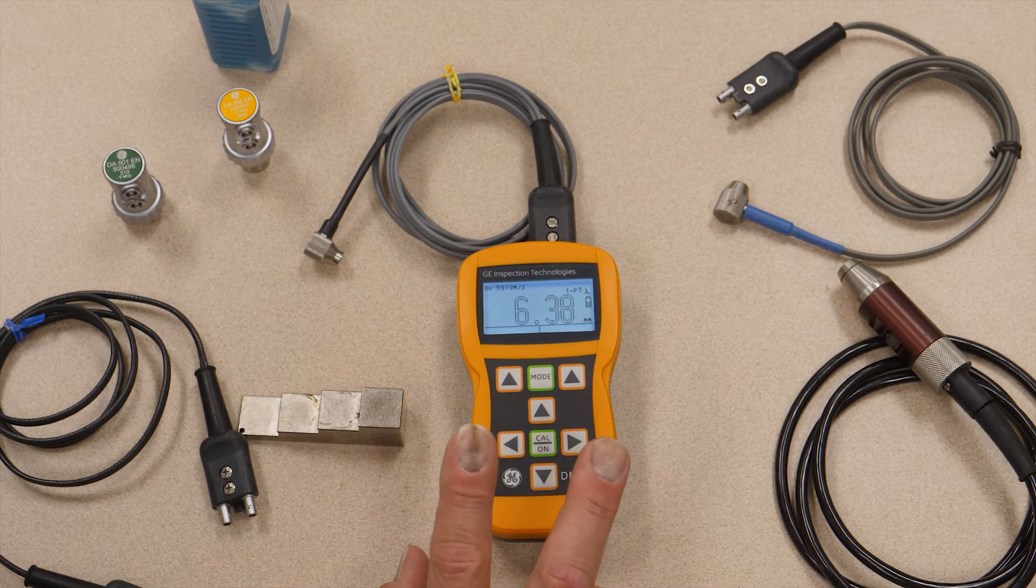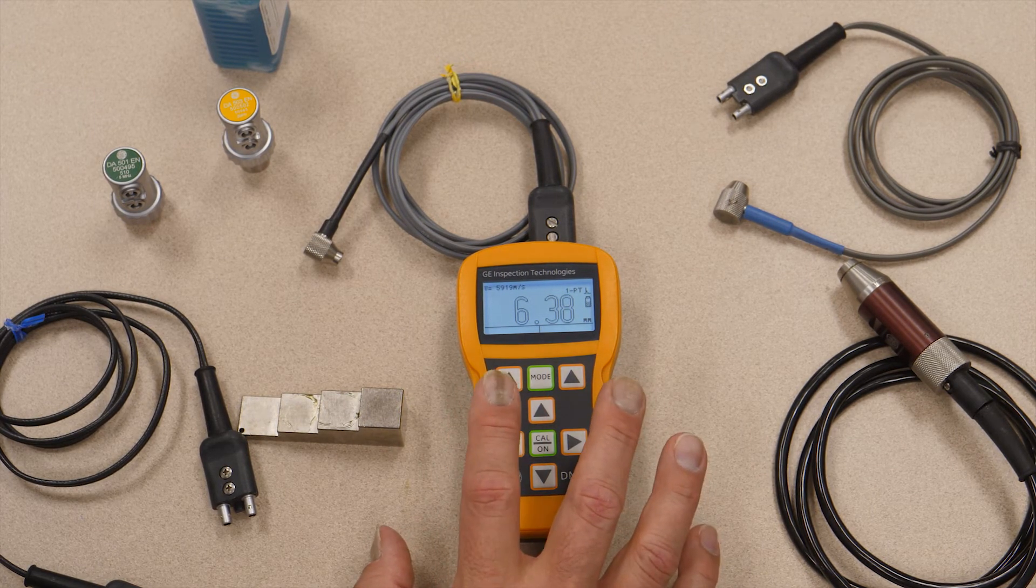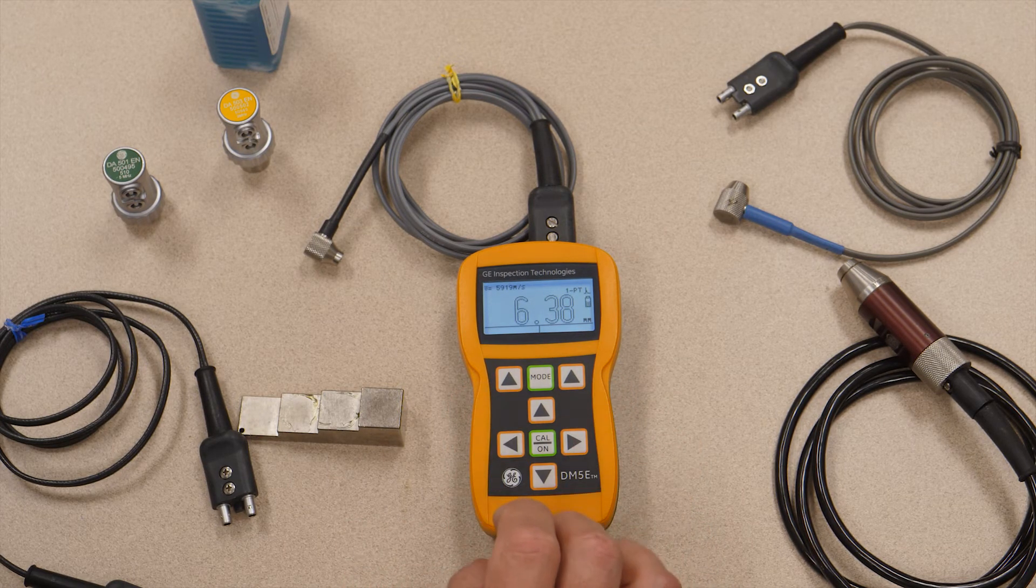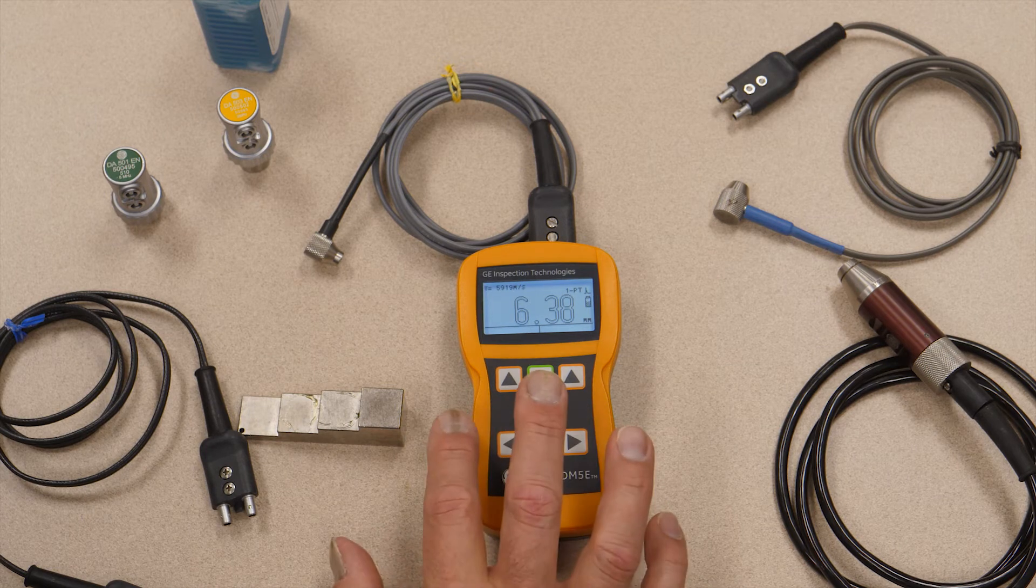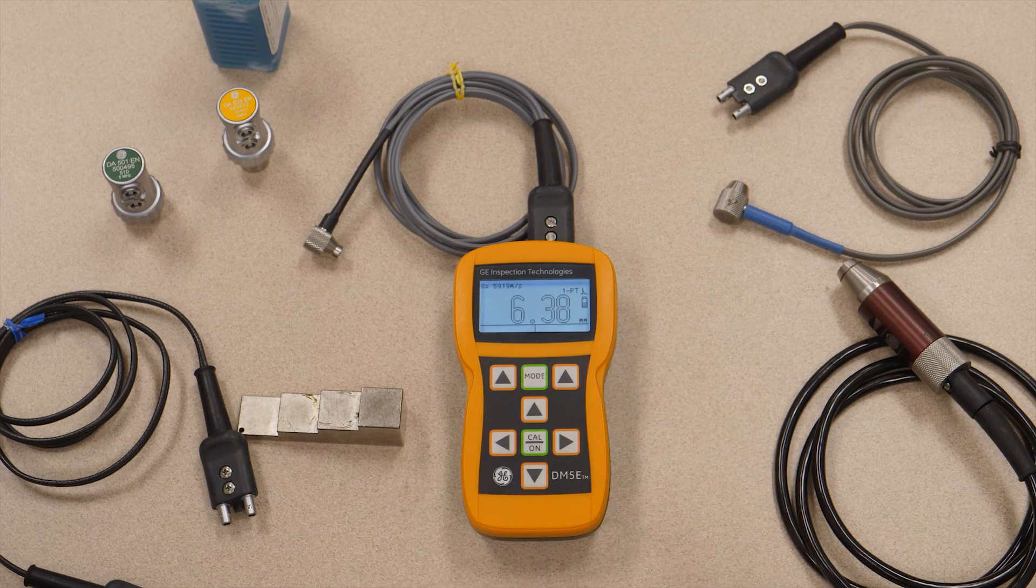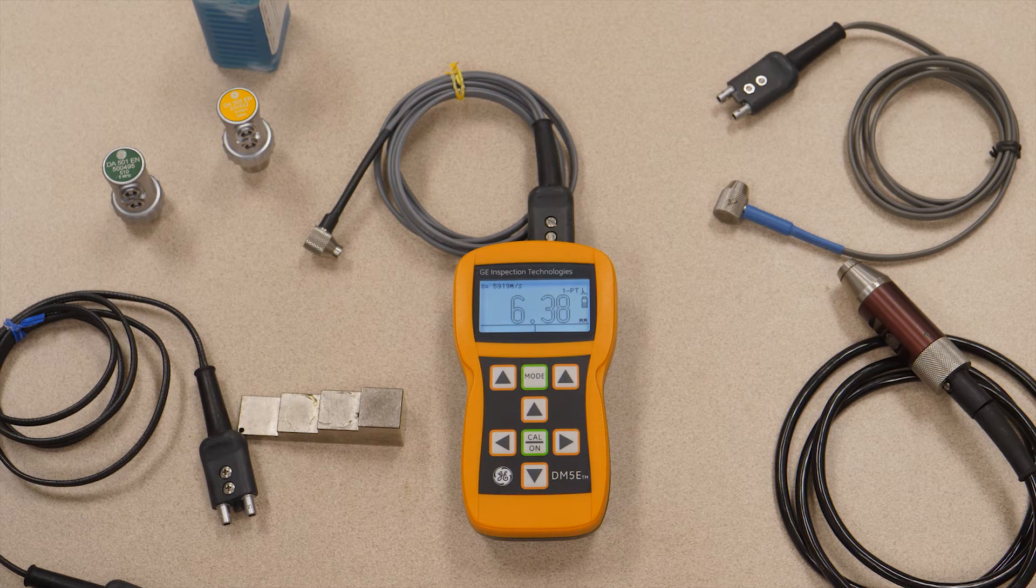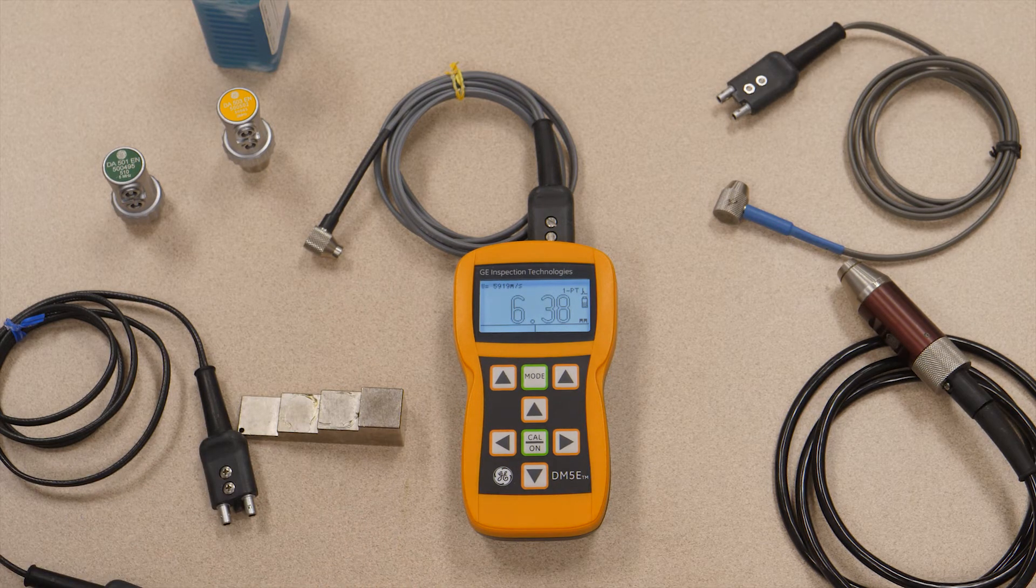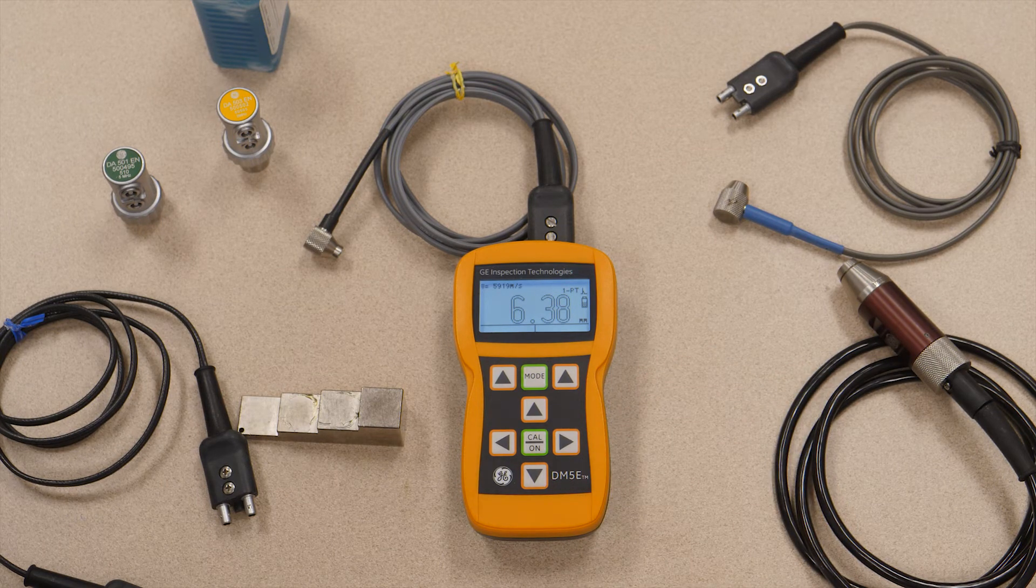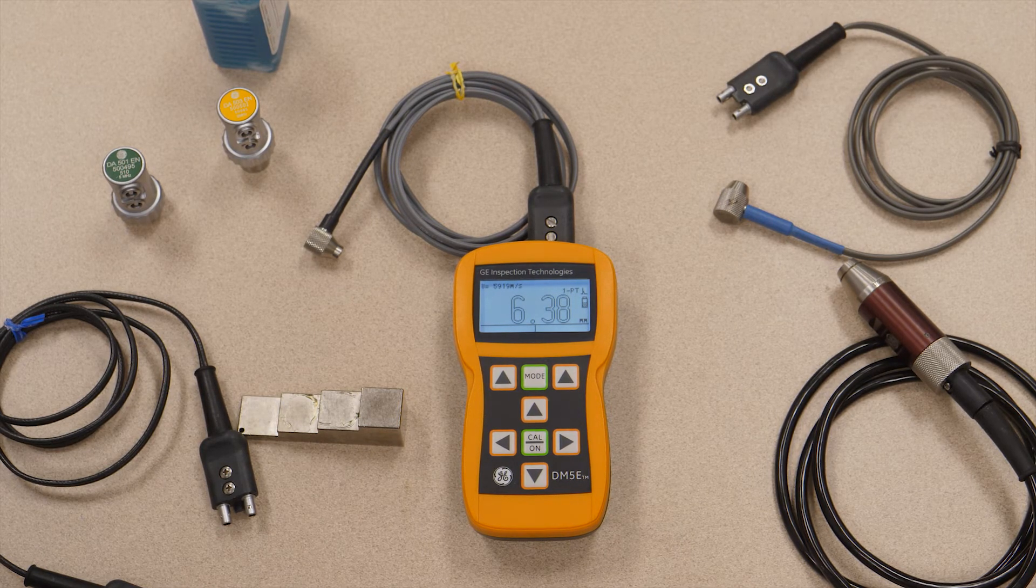Two options that we should talk about for the DM5E. Number one is data recorder. The instrument is capable of being set up with data recorder files, either lists or grids. As you're taking measurements, you store the data in the instrument. You can later take the instrument back, connect it to a PC. You can use our Ultramate software or we also include an Excel macro that allows you to pull the data recorder readings into either an Excel spreadsheet or bring them into our Ultramate thickness data management software.